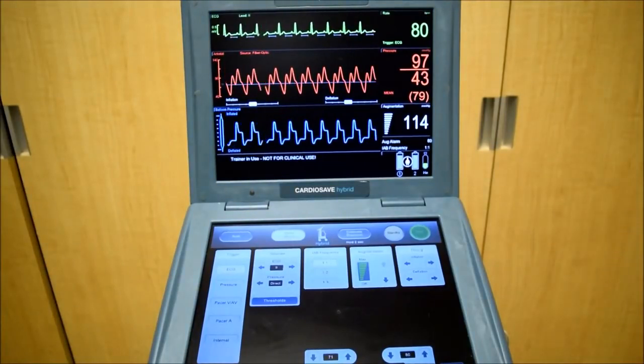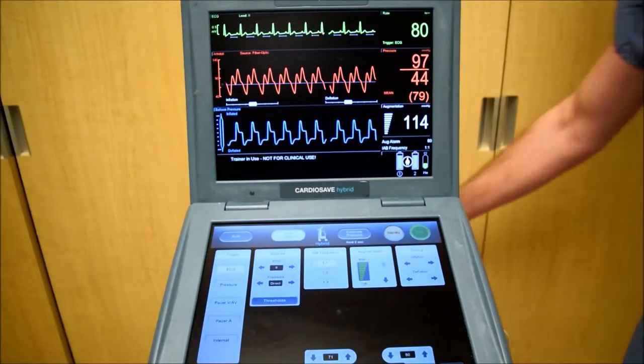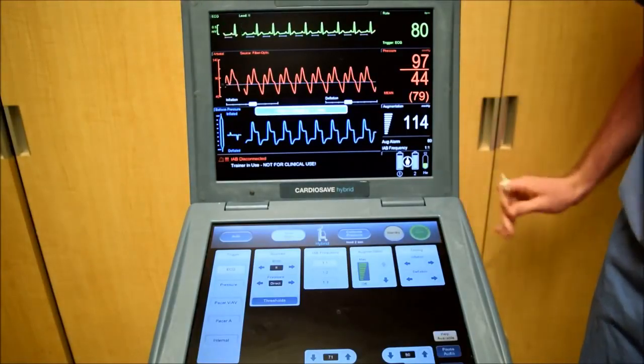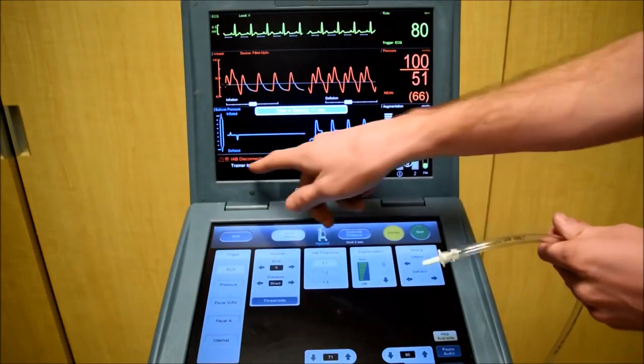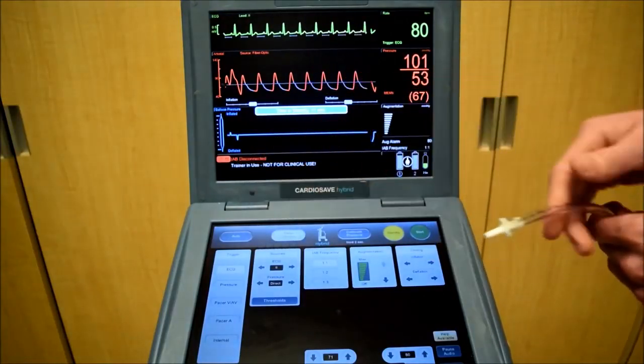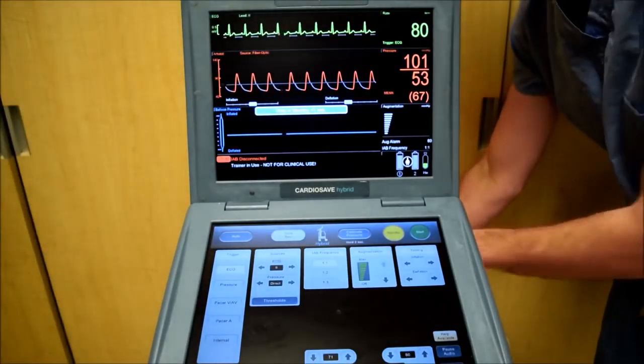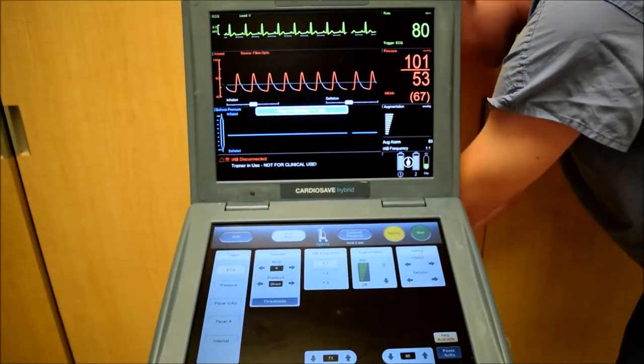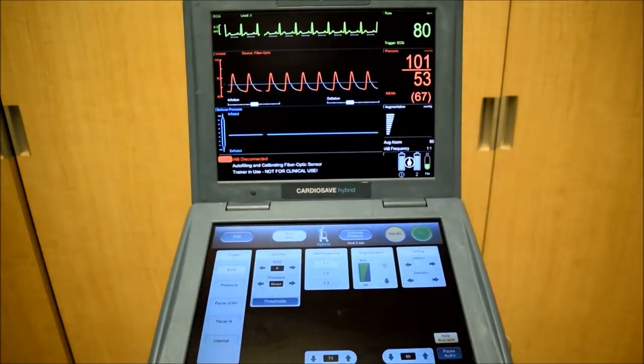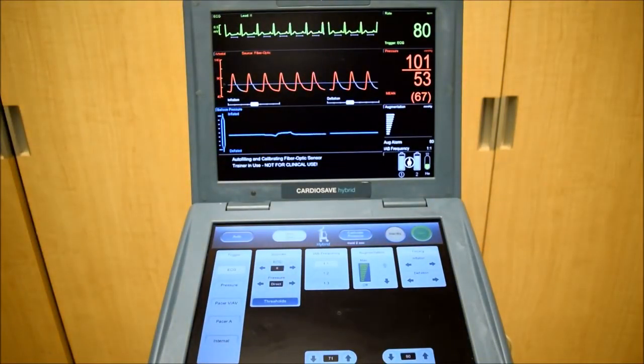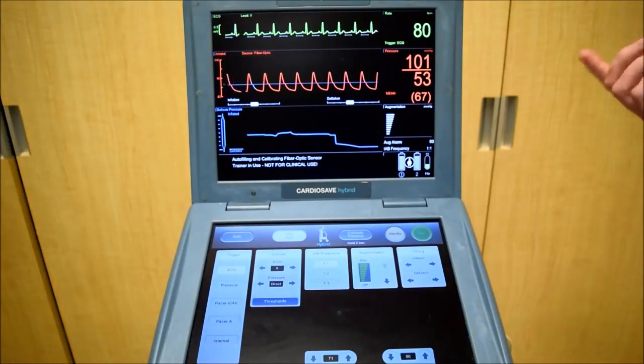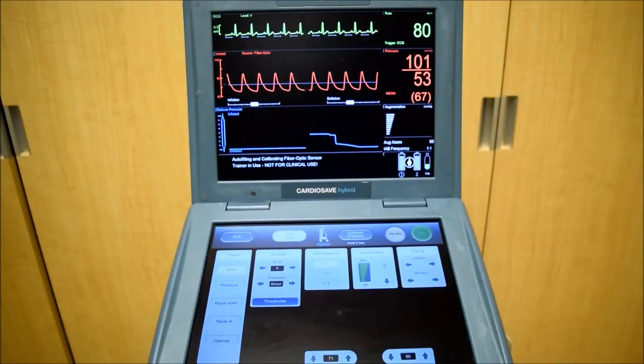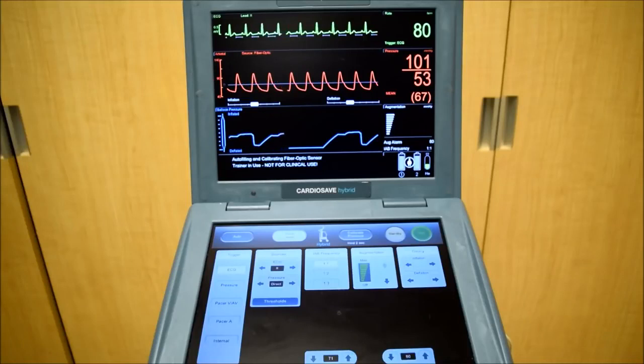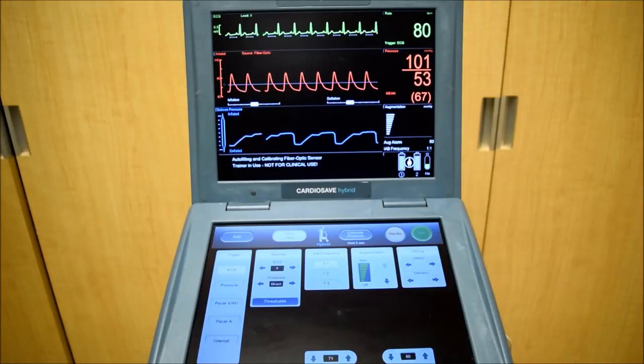And then another alarm you may encounter is if the balloon becomes unconnected. I've disconnected the balloon, an alarm appears. Balloon pump disconnected. Reconnect the balloon and restart the balloon. After you restart it, it'll need to go through its calibration sequence again. Once it goes through the calibration sequence, it'll start up again.